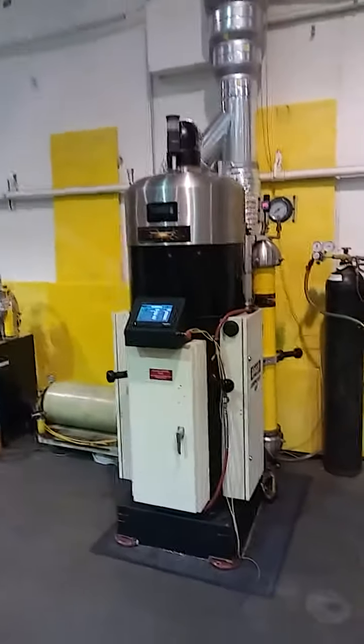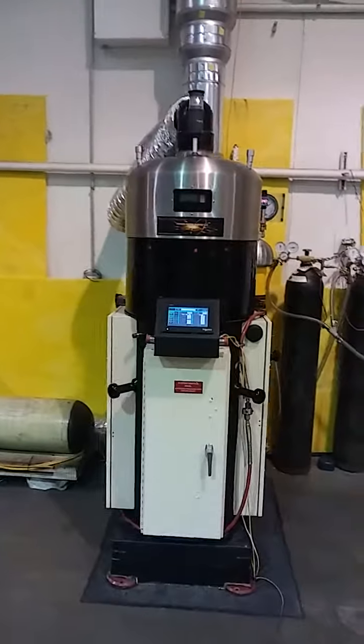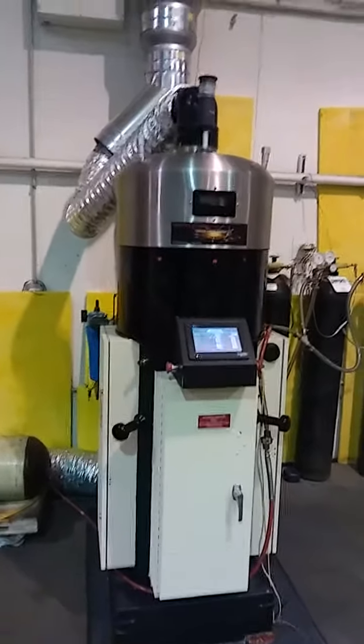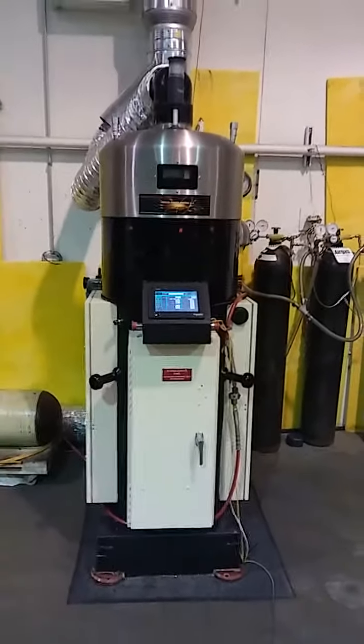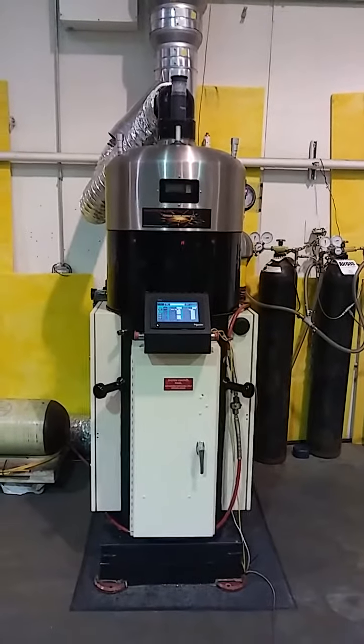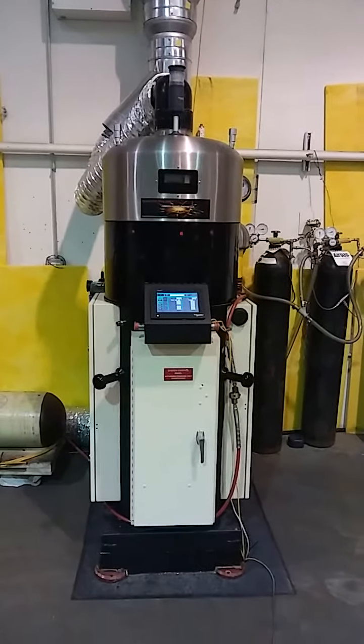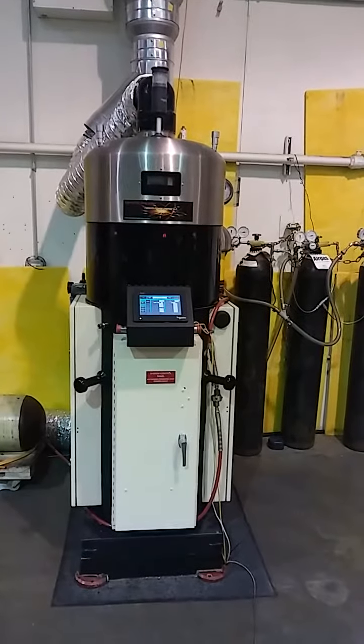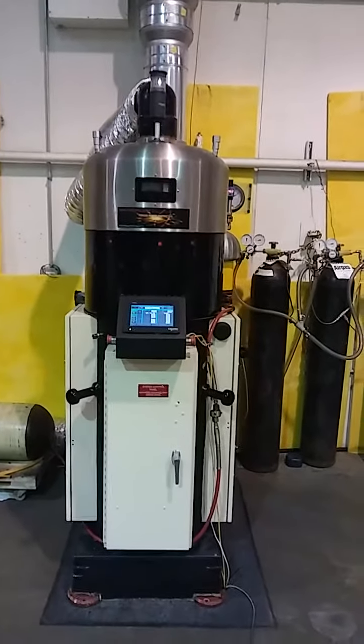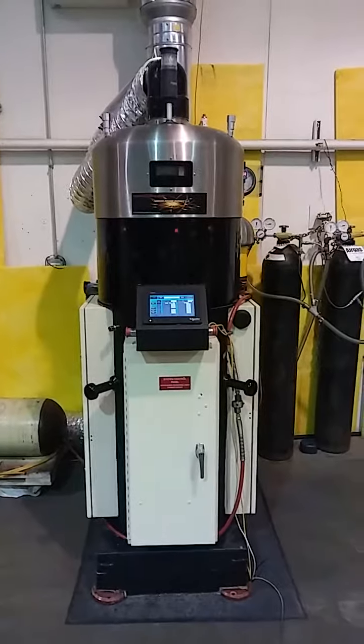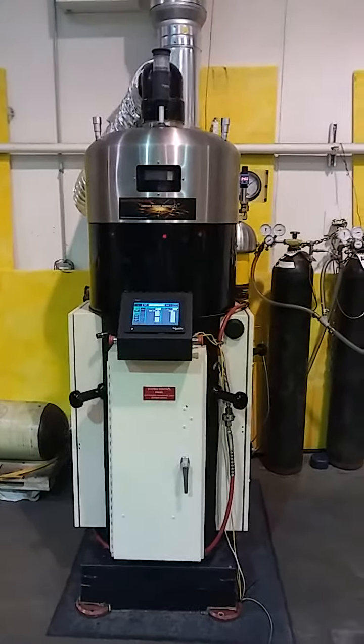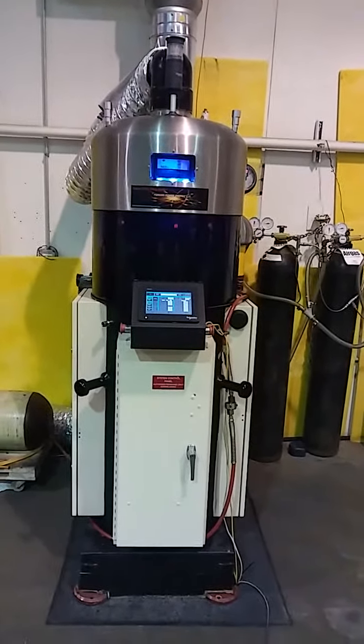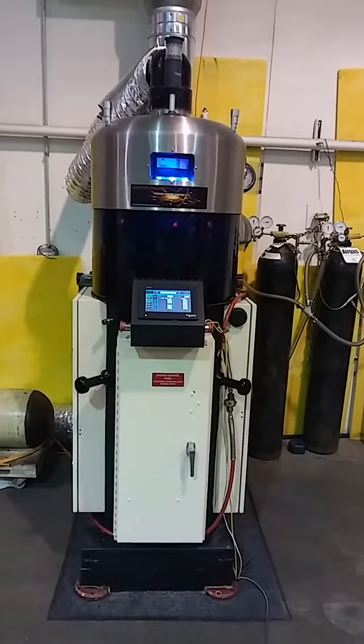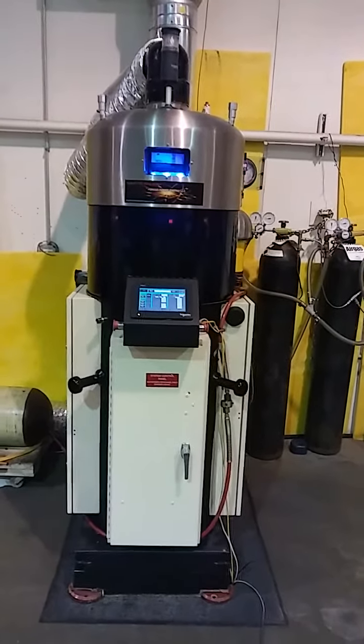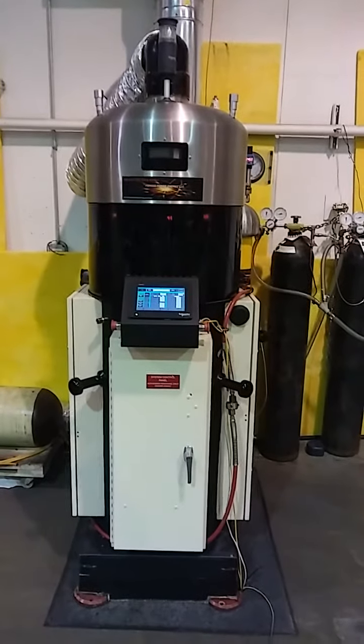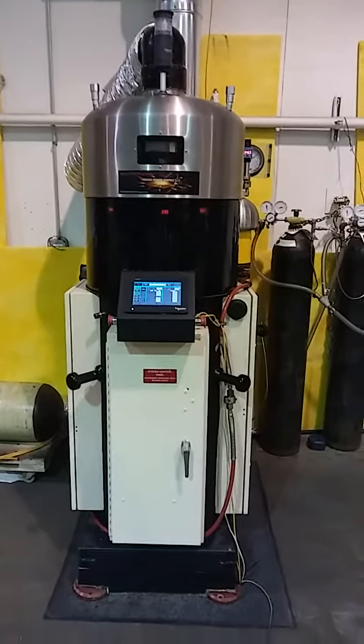Right now the coolant pump is running. It's the first thing that starts, looks for pressure and flow. And once that's achieved, it times out, and then the gas valve is open after it does a blowdown sequence. The blue light's flashing because the oil pump is energized now, looking for pressure and flow. These are independent pumps. Now the machine's running.